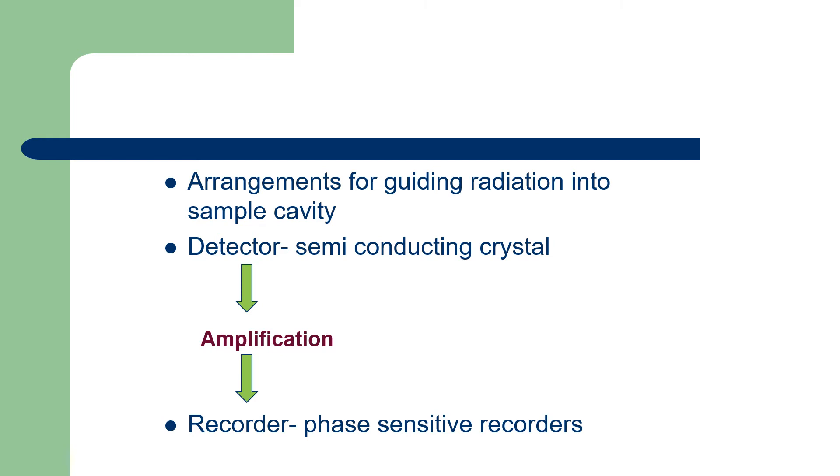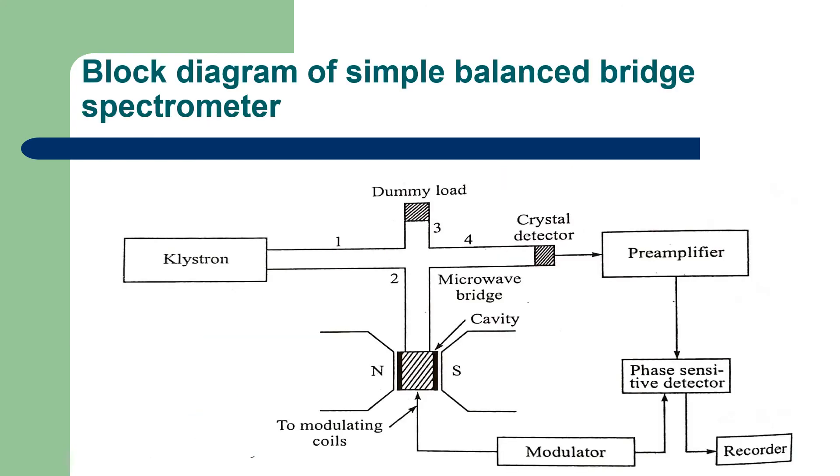Phase sensitive recorders are normally used in this ESR spectrometer. The block diagram of simple balanced bridge spectrometer is shown in the figure. Here we can see our source, klystron, then the electromagnet with pole pieces N and S, then a microwave bridge, then a preamplifier, then phase sensitive detector, then modulator and recorder.